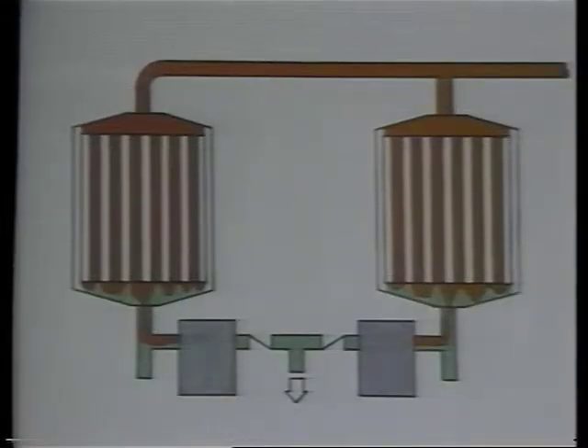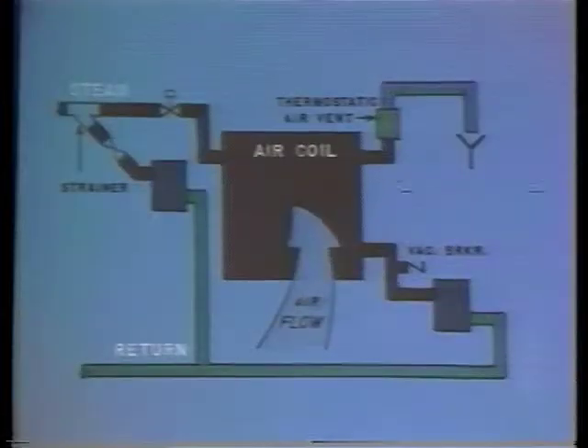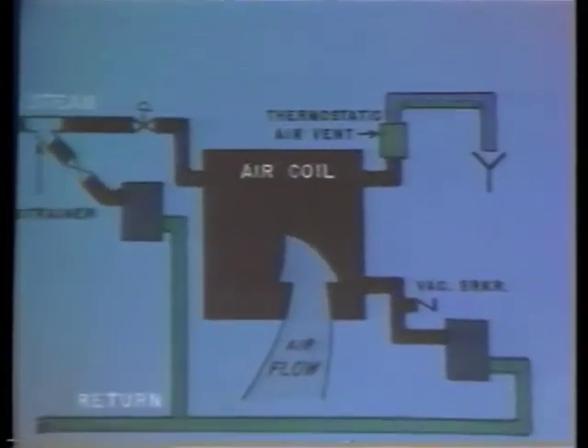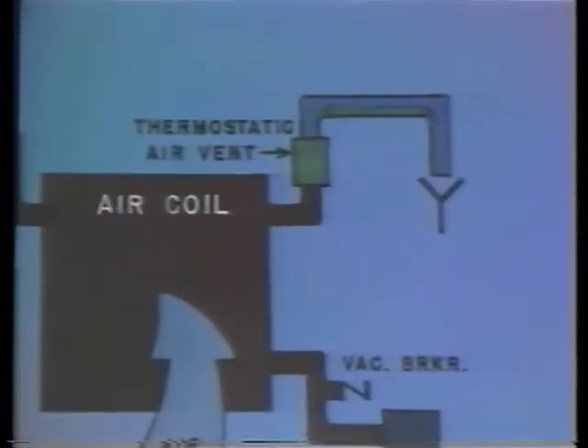Air coils, like all steam-heated pieces of heat transfer equipment, should be individually trapped. If two coils are group-trapped and the first coil has a higher load, a greater pressure drop across the first coil will exist. This results in partial flooding of the first coil. Again, if the coil is of the grid type of construction, a thermostatic air vent should be installed at the high point of the discharge manifold.